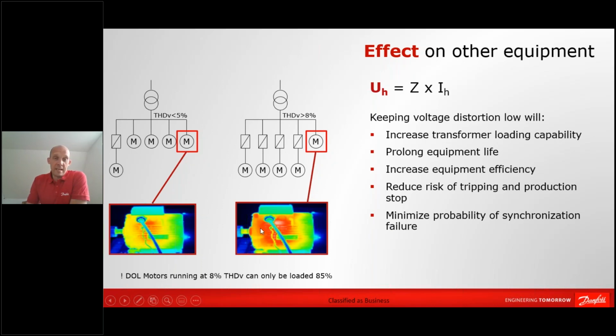So the flip side of harmonics is actually not something that makes motors start falling out of synchronism. It's not something that causes a sudden production stop. The typical side effect of harmonics is reduced energy efficiency of your installation. In this specific case on the motor, it probably means that the bearing in the motor will wear out because the bearing is becoming a lot hotter than it was before.